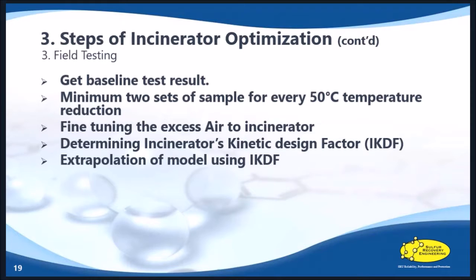However, it might be around 60 feet or 100 feet, depends. So it warrants different safety standards, for example, fire brigade watch or crane or something. In general, the program consists of 2 to 3 days of field testing work in SRE. SRE collects 2 duplicate samples for every 50 degrees centigrade temperature reduction at stack top. And these 2 duplicate samples are necessary to get representative results.